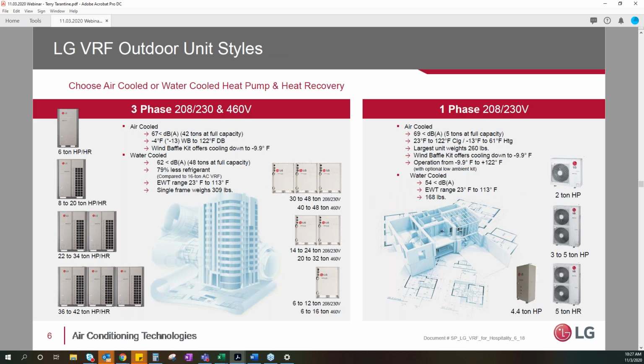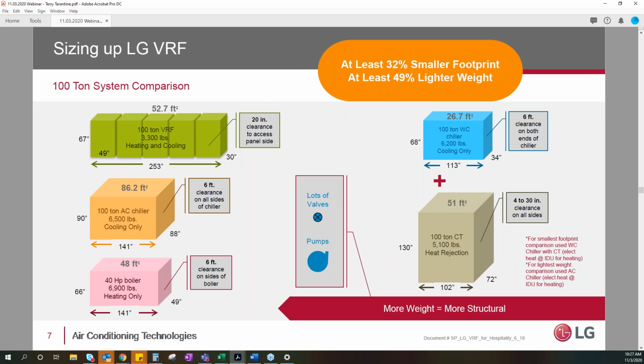VRF, again, small footprint, typically up on roofs. We can run extremely long line set lengths. And we show here that even the water source side of it, very compact little units, and they are modular. We just couple them together to get the efficiencies we're looking for. They're also available in single phase, and we're seeing single phase smaller units becoming much more popular. We've got some operations going down in Florida right now, large towers, hundreds of tons per tower, and they're all individual single phase heat pumps. So again, it's becoming a much more popular side.